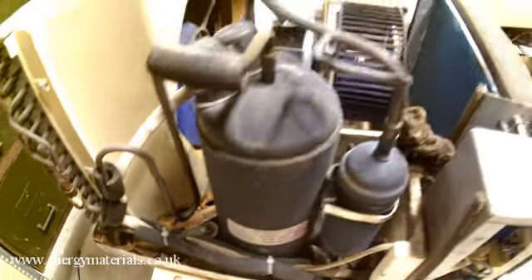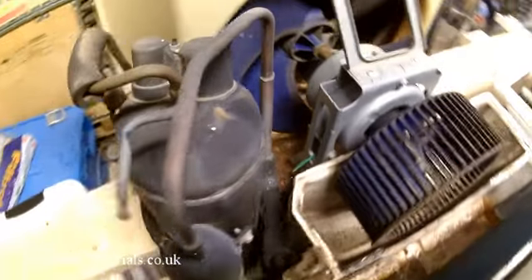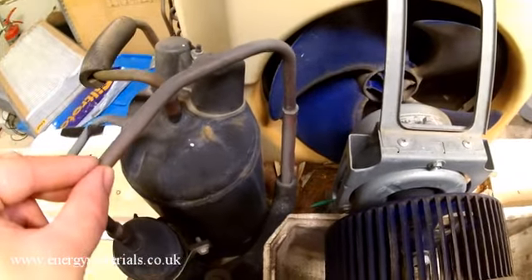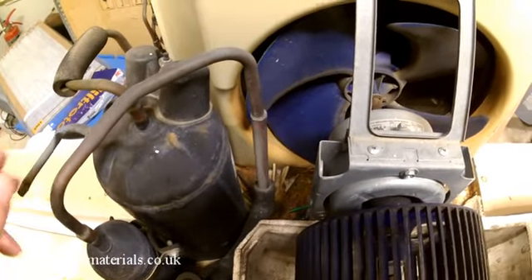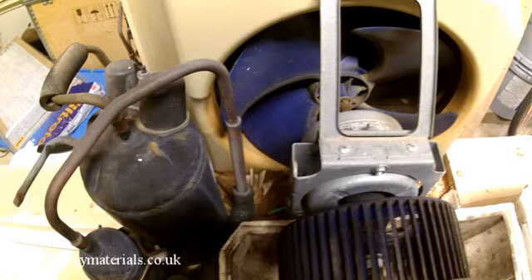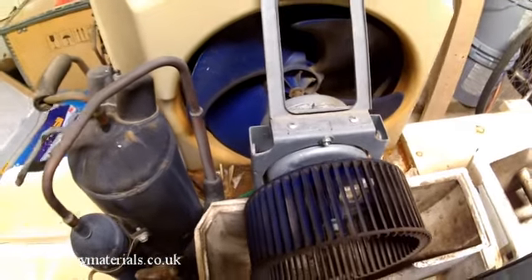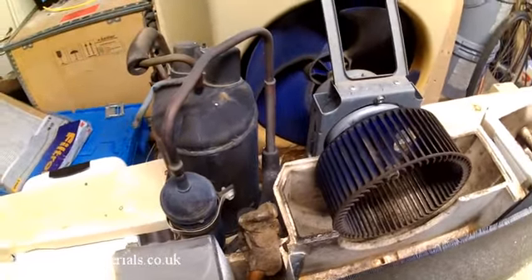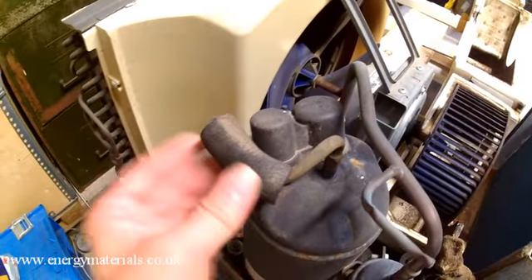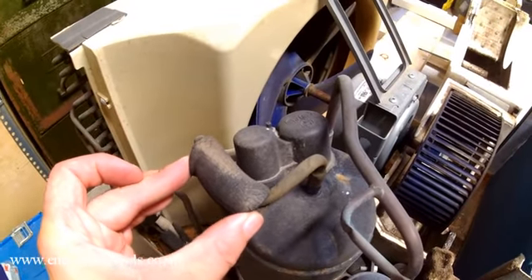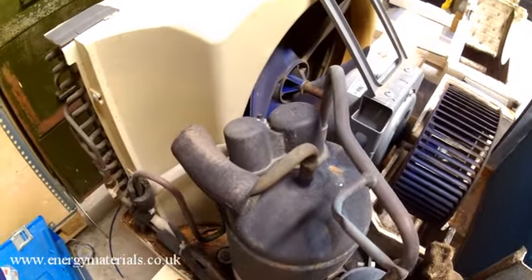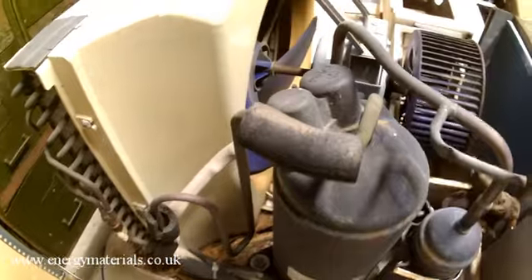So we're going to have to use some special attachments to extract the refrigerant from this system, as we're going to reuse it and put it back into the AC unit once we've done the split. So there's a couple of interesting points on here as well. We can see some insulation. Not quite sure what this 2.5 inch section served. Maybe it was like a vibration thing with the outer casing.